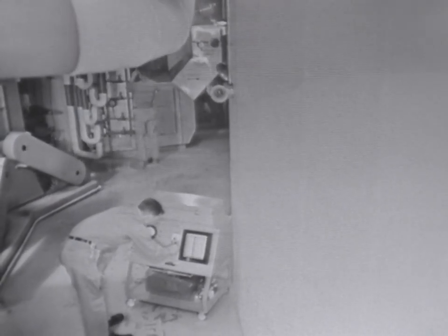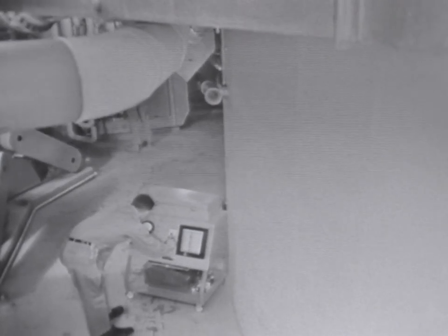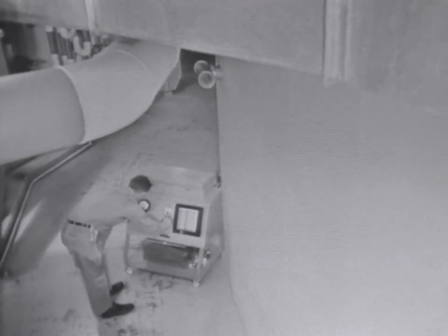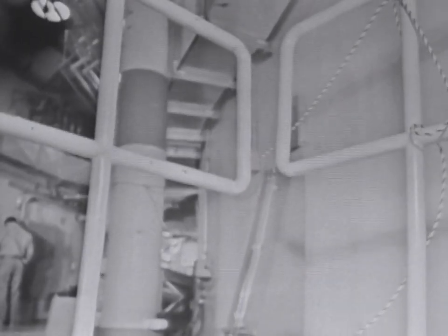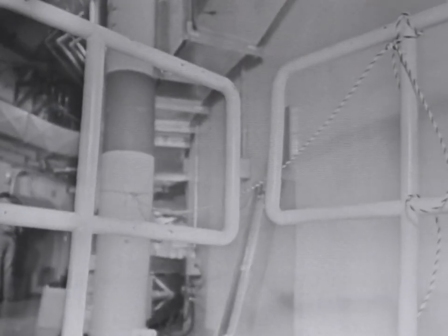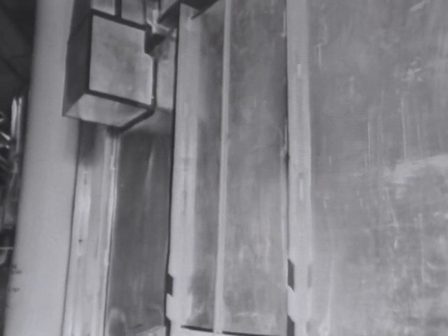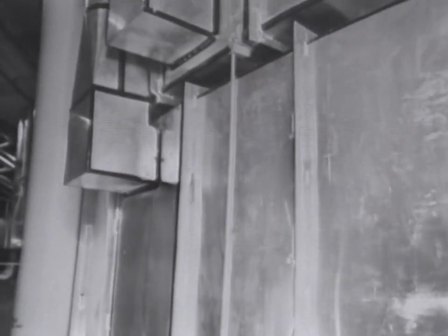The bottom of the primary tank is about 40 feet below floor level in this building. Here in the sub-basement, you can see on the right the outer surface of the heavy concrete radiation shield, which completely surrounds the primary tank. The air ducts carry cooling air to the shield, needed to remove the heat generated by absorption of neutrons and gamma rays from the primary tank.